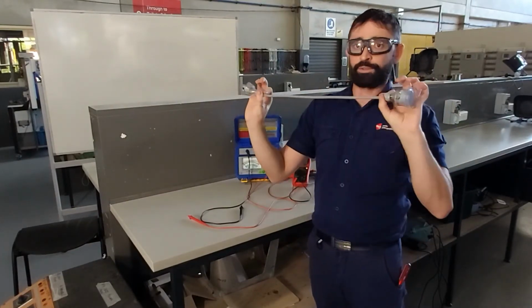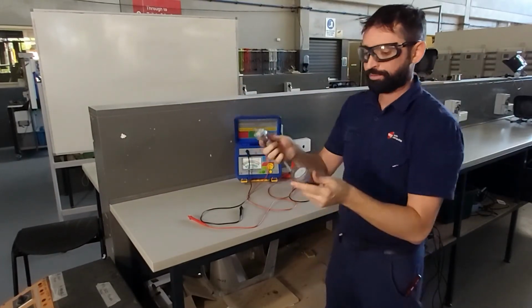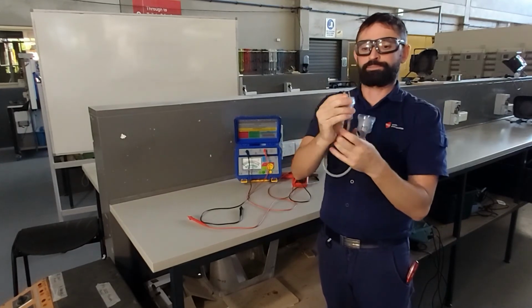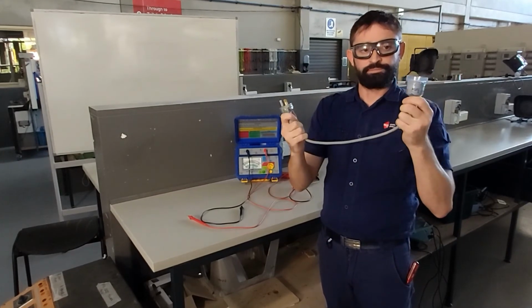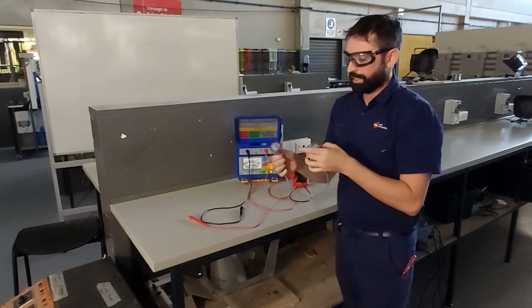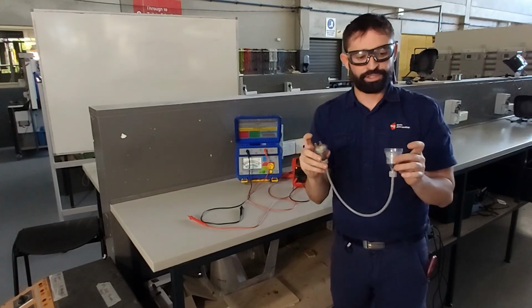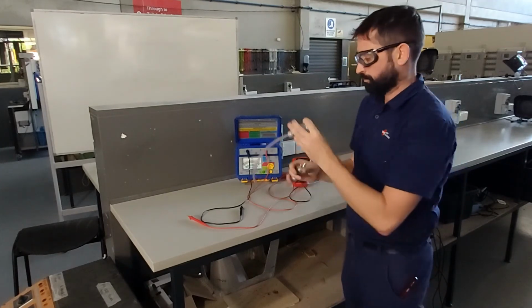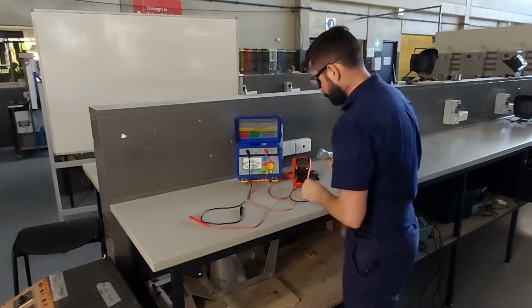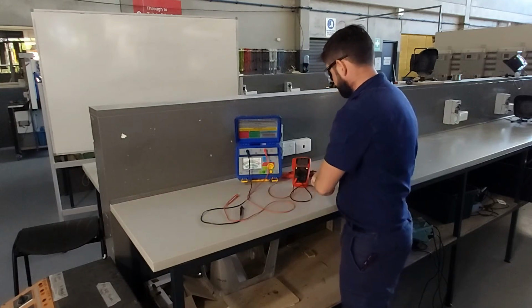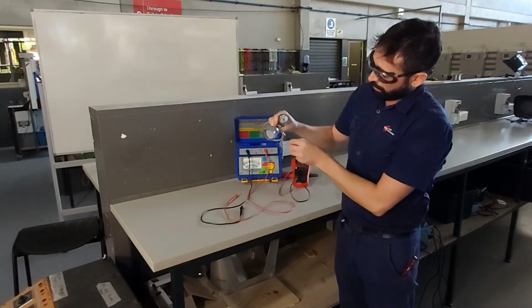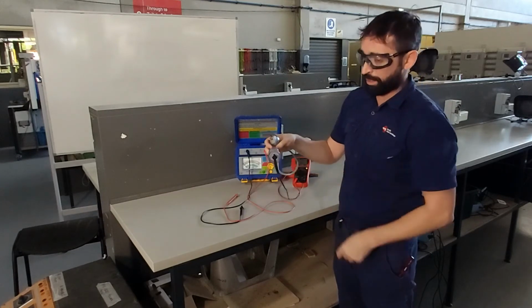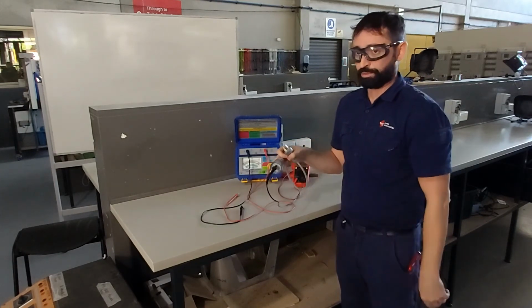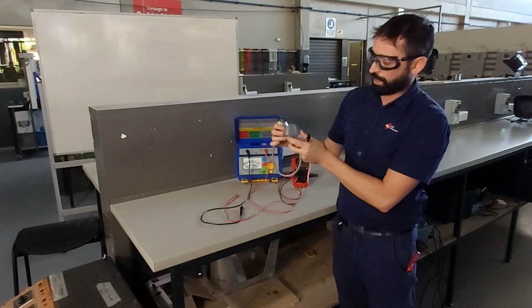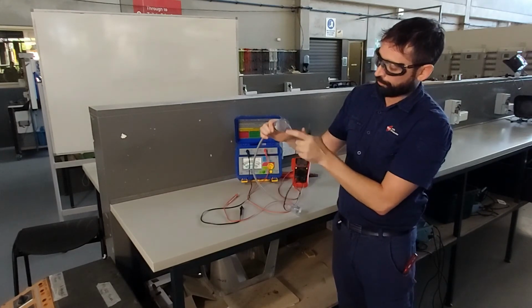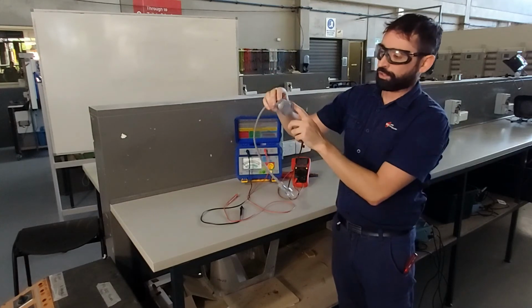Now the final test that we do is the polarity test. Okay, we have to do a polarity test on this because we installed this plug top and we installed this socket. Okay, so we've already done the earth. We measured the earth in the first test, the earth resistance, so we know that earth goes to earth. Now it's very important that we don't just get our multimeter probes and go from blue cable to blue cable, because obviously that's only going to tell us blue to blue is going correct. What we need to do is make sure that we're going from active to active, neutral to neutral, because these terminals are marked.